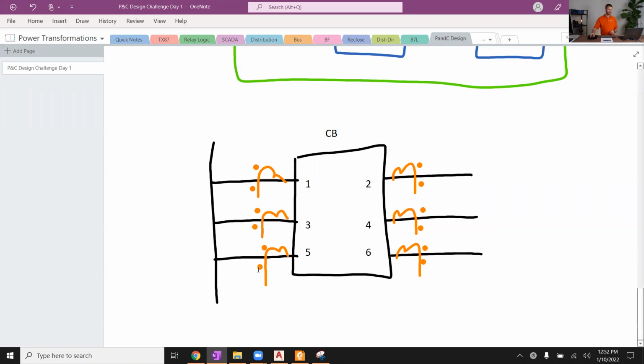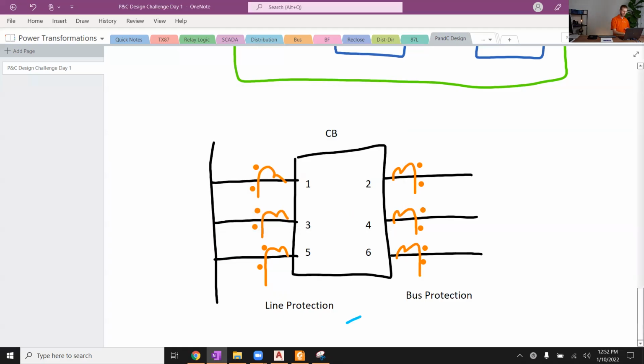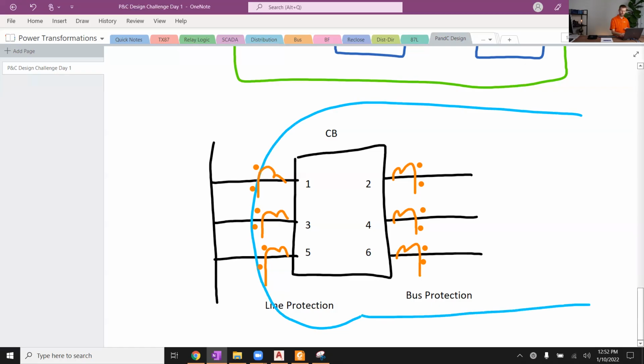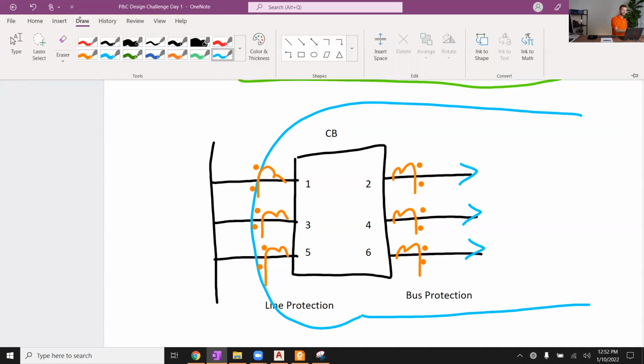you're going to be using these 3 CTs for your line protection, for your line relay. You're going to use these 3 CTs on the other side of the breaker for your bus protection, for your bus relaying purposes. And what you're going to see is this overlapping zone of protection. Just to kind of give you the concept, I might remove these lines later, but your line protection is going to be protecting that direction on the power system, right? These are lines continuing on, but then from the bus protection side, that's going to be different.